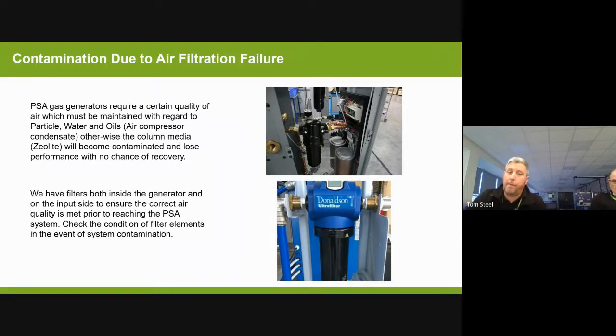We've got filters inside and outside of the generator. I can't stress this enough. The generators are very, very good, but you need to ensure everything is maintained annually and to the specification of the compressor specifications, the filtration, and also for the oxygen generator itself, to ensure that the quality of gas coming out is satisfactory.